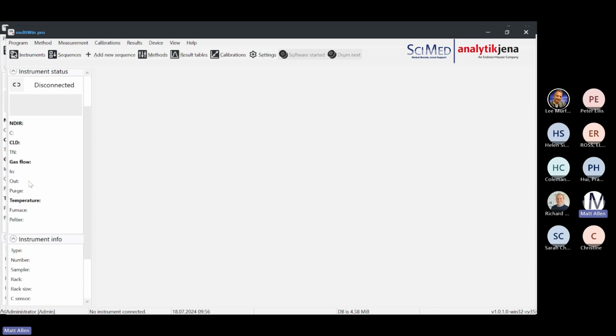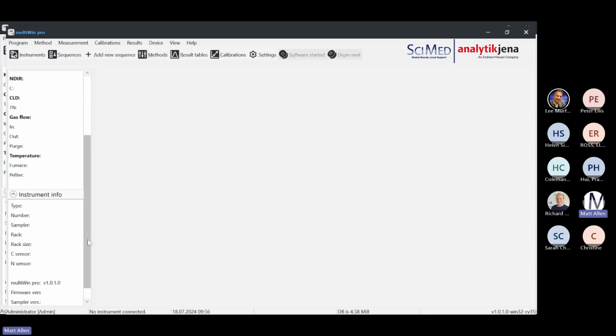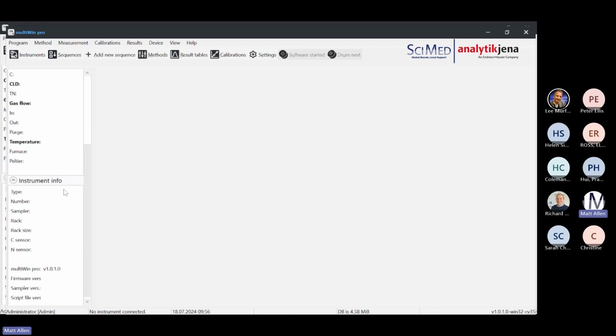So you know if you've got a leak, it should normally be 160 mils going in, and 160 plus or minus 5 coming out. If we're looking at NPOC, then we'll have the purge value here for purging off any inorganics. Next one down is the temperature, which feeds back the furnace temperature and the Peltier cooler. Just below that, we've got the instrument info.